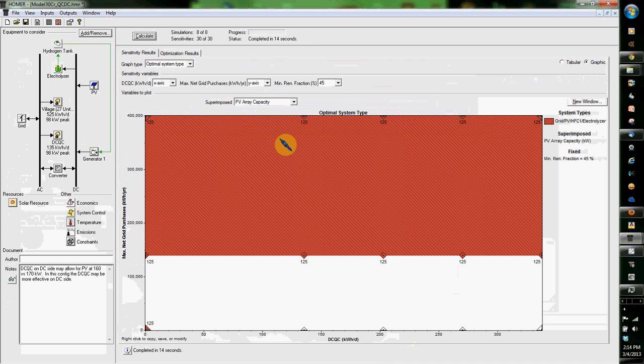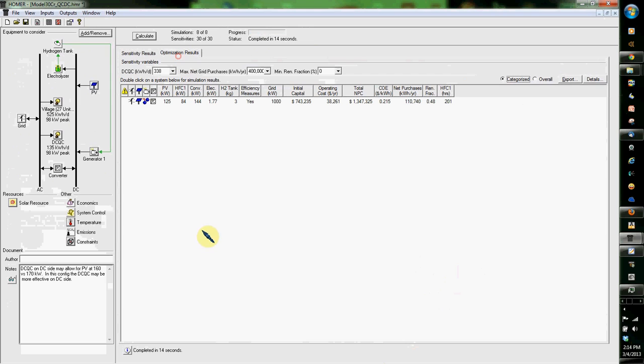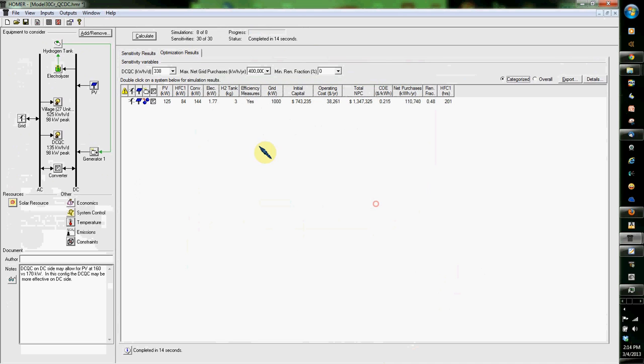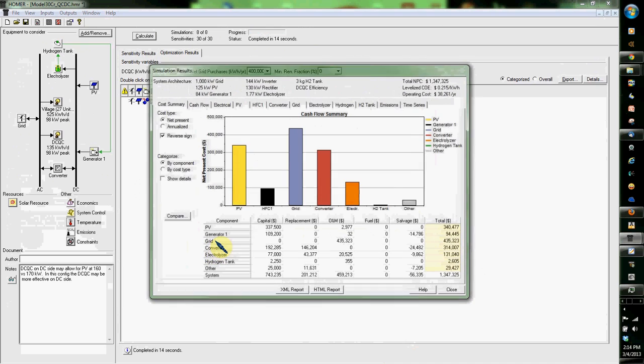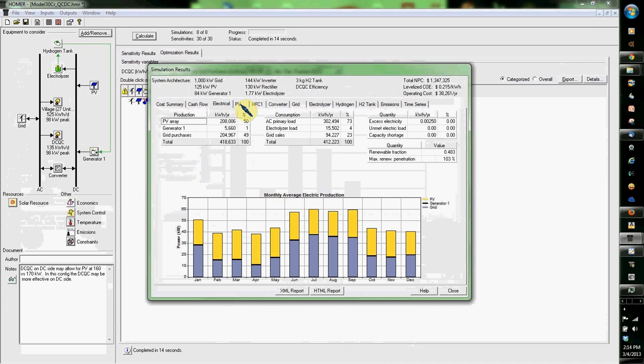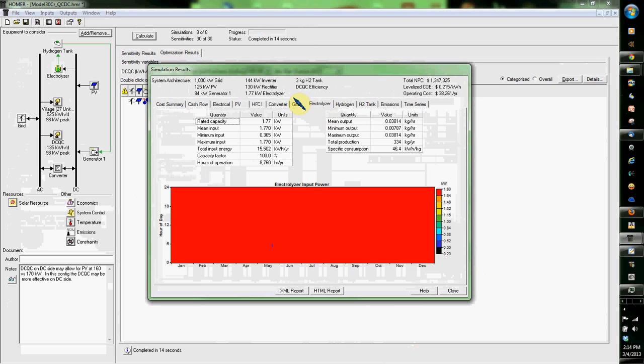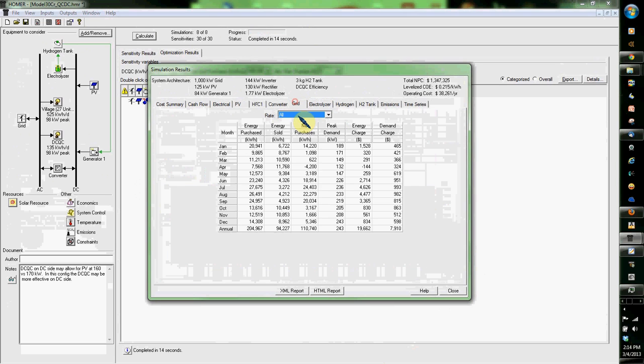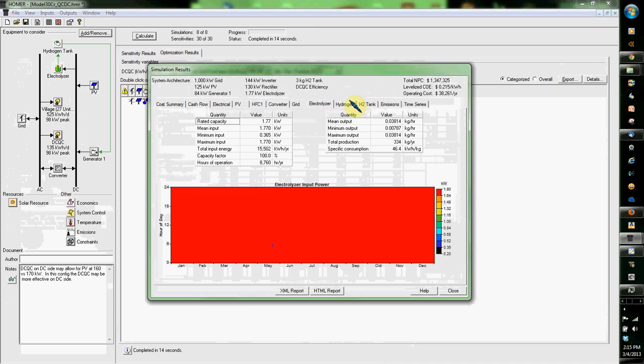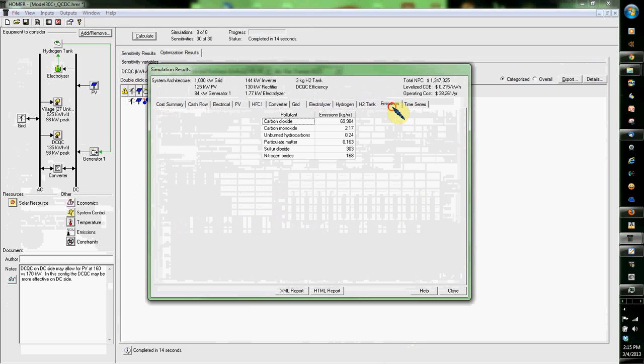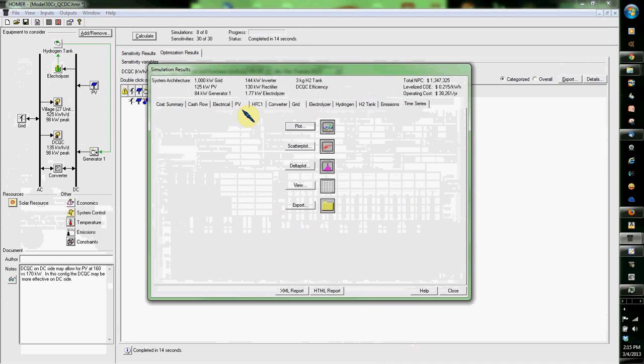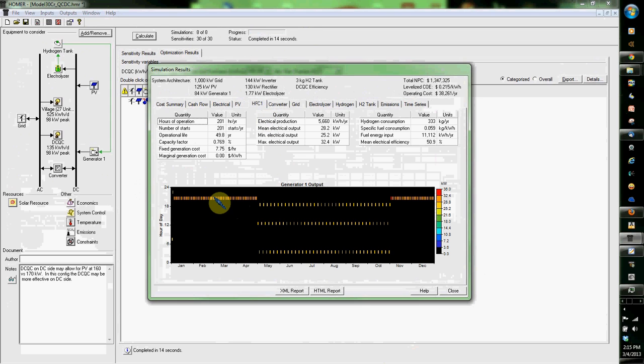Your runtime is anticipated to be a lot less, eight seconds, very nice. And then you see right here, if I want to look at it and see what was the better one, it likes 125, it definitely likes 84. The rest of the stuff is pretty static, so it has no choice. When I look at these, I see my electrical looks very good. When I look at grid, net grid purchase is better annually, but not where I want to see it. Bigger is not always better. If you watch my previous video, you'll notice I used a 63 kilowatt fuel cell. This is nice, it lets you see how it's functioning, and then the level output.